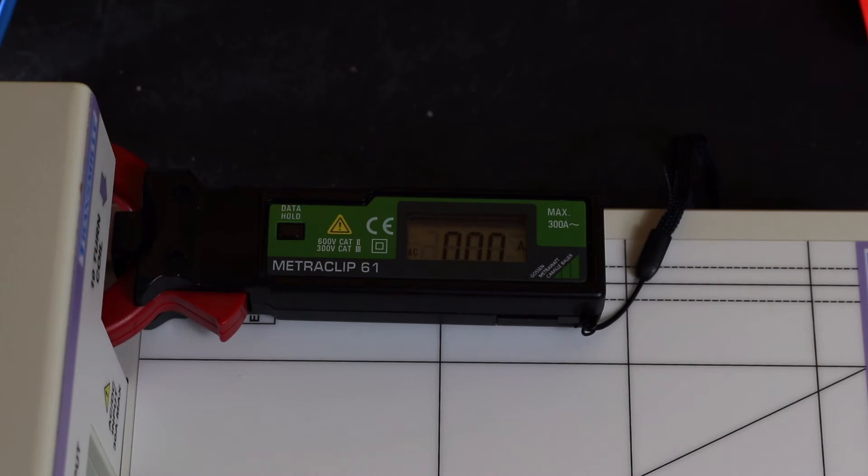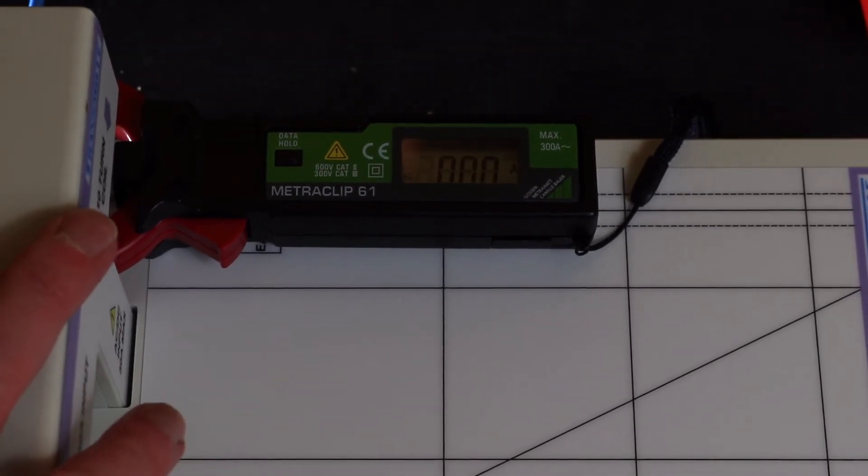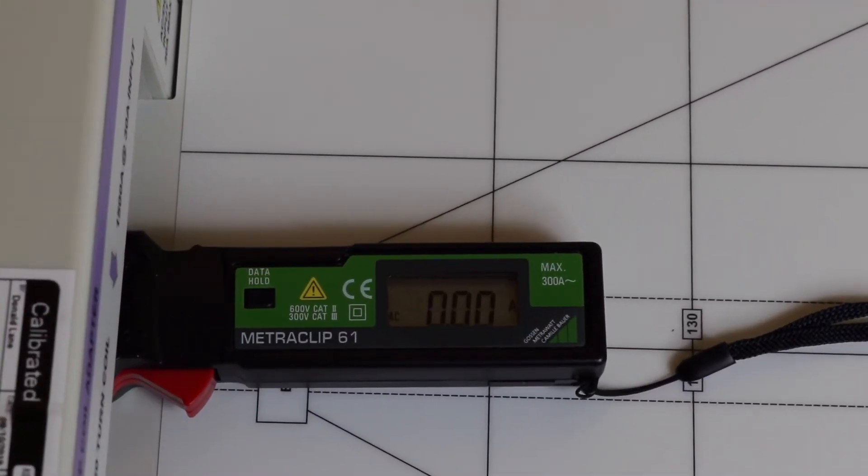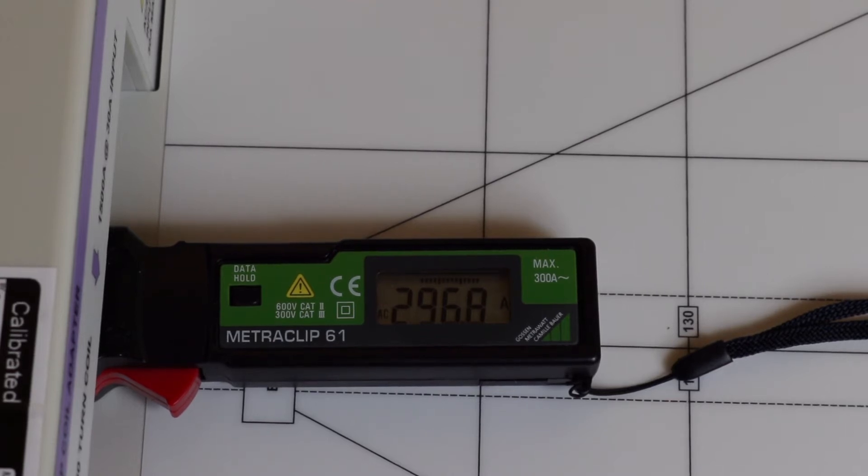I'm just going to flip this over and put it onto the central coil and take this up to its max 300 amps. Okay so we've just reset this onto the center coil. So this is now a 50 to 1 amp coil. So I put 6 amps in to get 300 amps out and we're reading 296.8.